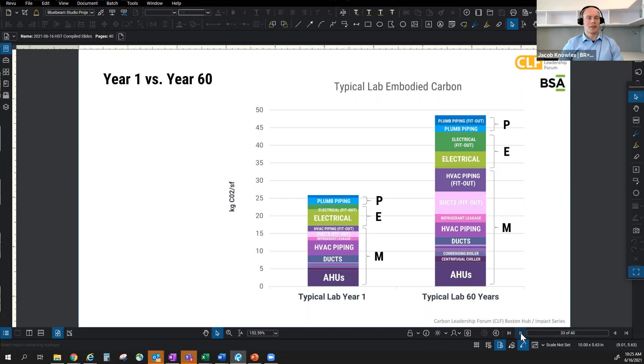One of the other things we wanted to look at is higher performing lab designs, like using chilled beams instead of all-air systems. We wanted to make sure that proved out not just in operational carbon savings, but also embodied carbon savings. We compared a conventional all-air core and shell developer lab versus a chilled beam one, and with the major reduction in air handlers and ducts, there's a significant savings on embodied carbon. Granted, it's not a game changer. You might be targeting close to carbon neutral for operation and only getting a 10 or 15% reduction in embodied carbon of the MEP systems, but at least they're both headed in the same direction.